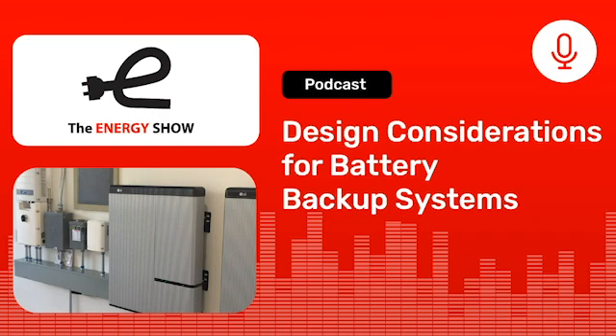You have to make sure about the essential loads you're connecting—this is probably the most challenging thing to figure out for every system—where are the circuits you want to back up? Is everything in the same electric panel outside the house near the meter? Or is there a sub panel in the bedroom, a sub panel in the kitchen, and a sub panel in the garage, each with a couple of circuits you have to wire in? Obviously, in the latter case, with 3 sub panels in the house, it's going to be a lot more electrical work to tie those things in.